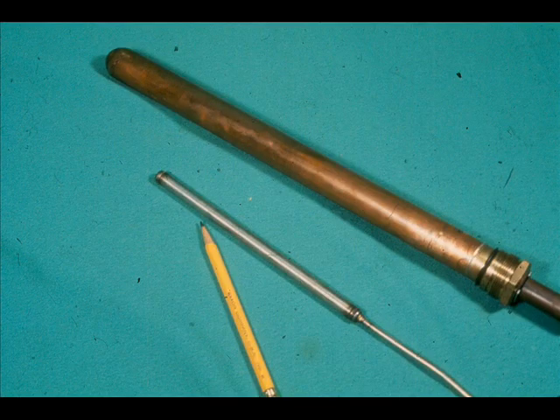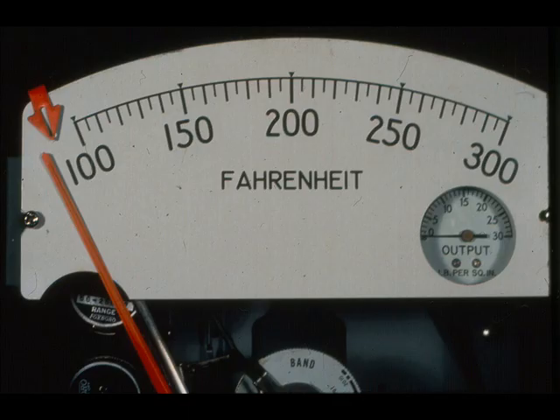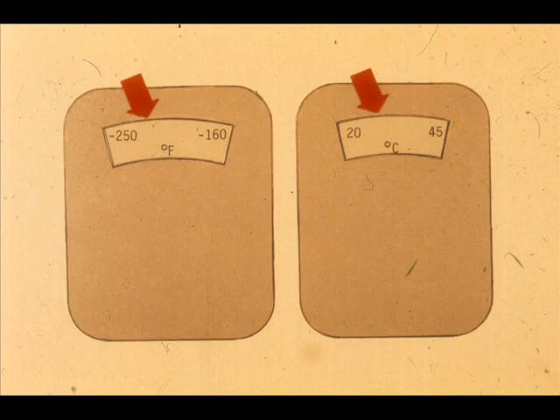The liquid fill systems use the smallest bulbs of any of the fill systems. This may be the determining factor in some installations. Since liquid expansion is linear within the range covered, the chart or scale of a liquid fill system is uniformly graduated. They may also be designed to have the narrowest range of any of the filled systems.